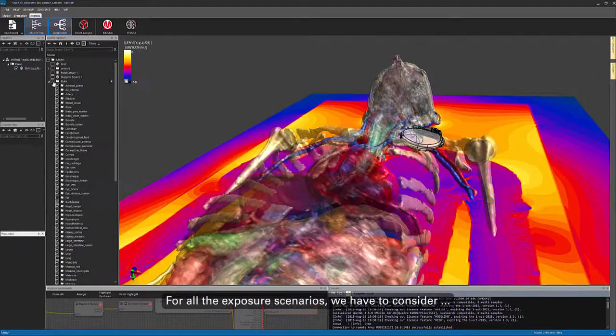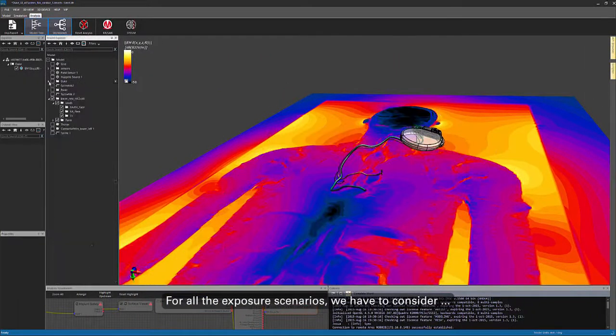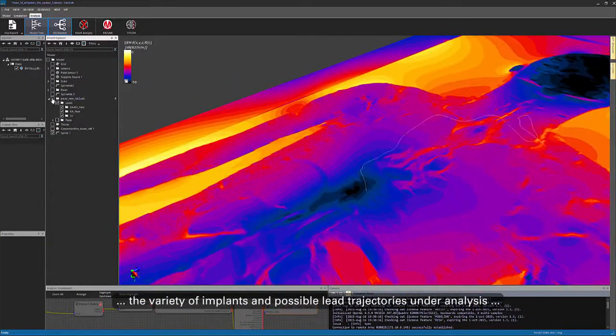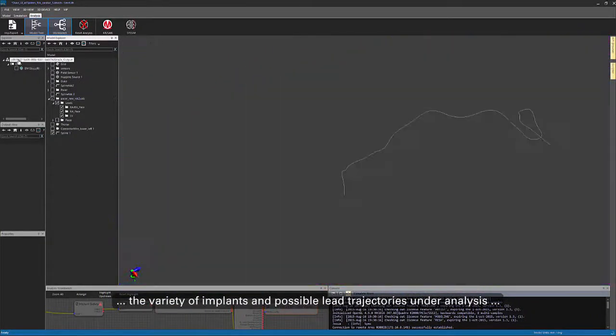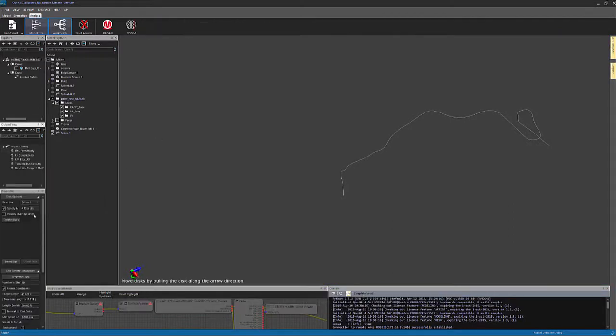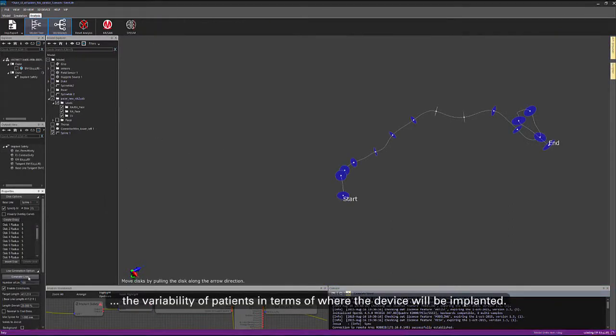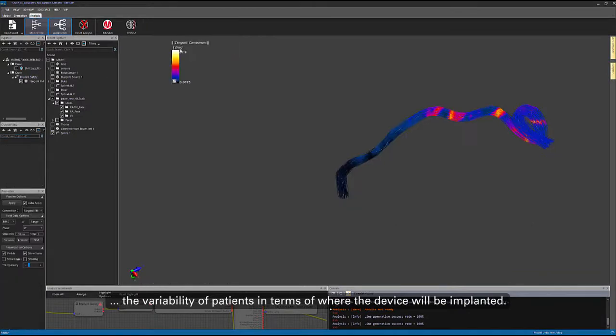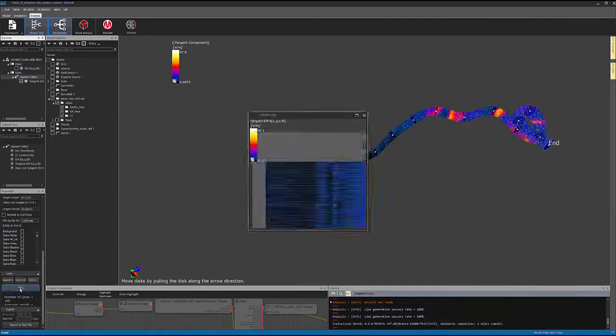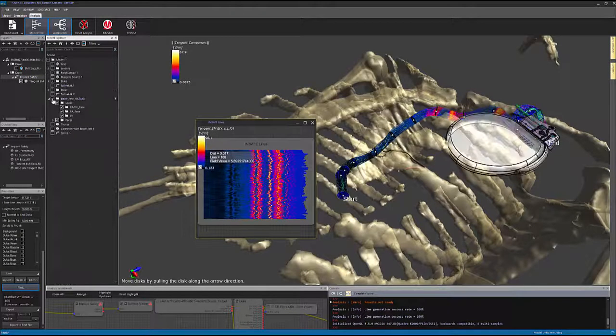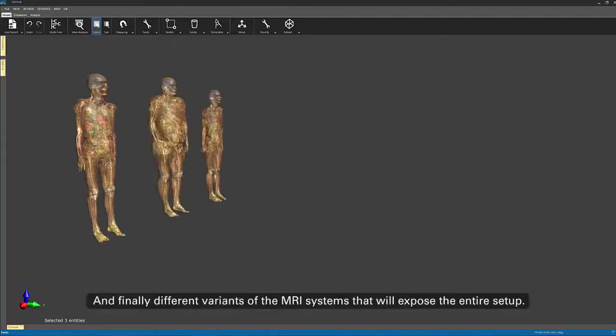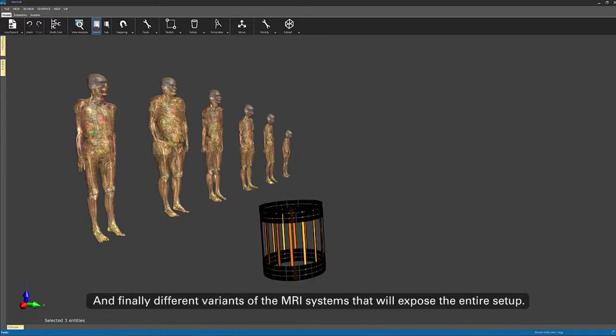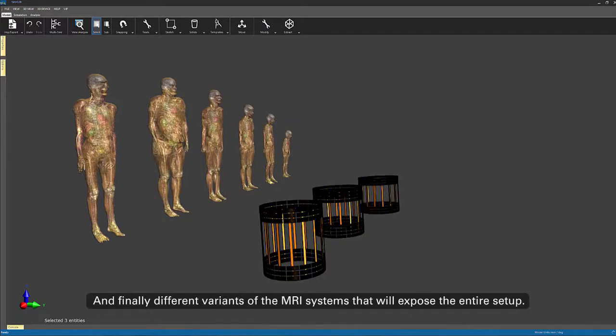For all the exposure scenarios we have to consider the variety of implants and possible lead trajectories under analysis, the variability of patients in terms of where the device will be implanted, and finally different variants of the MRI systems that will expose the entire setup.